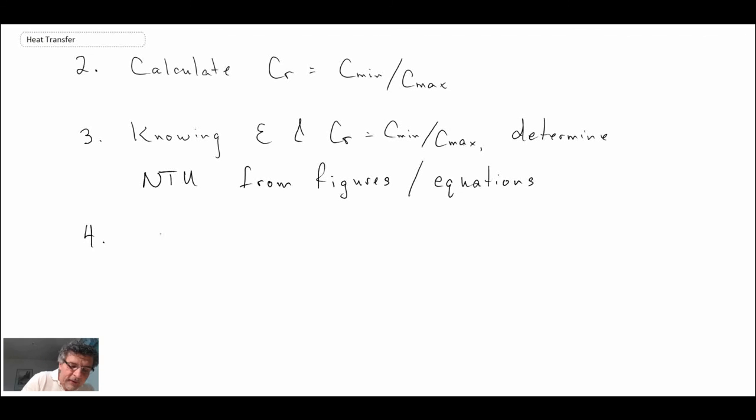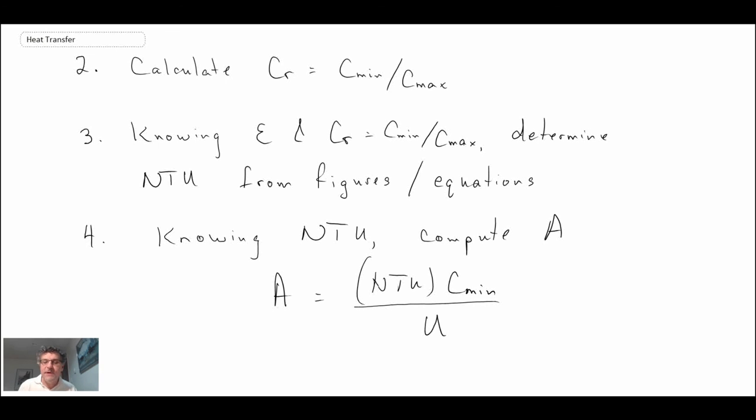And then finally, we're looking for the size. So knowing the number of transfer units, we can then get the area of the exchanger, which equals NTU times Cmin divided by the overall heat transfer coefficient U. So those are two different methodologies or procedures that you can use to apply effectiveness-NTU.